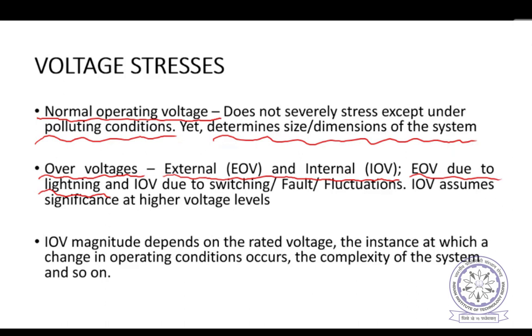And apart from that, there are internal over voltages, IOV. This is due to switching conditions, fault conditions or any fluctuations, which will cause certain oscillations on the transmission line. These are over and above the normal operating voltages. Even external voltages or internal voltages are over and above the operating voltages.